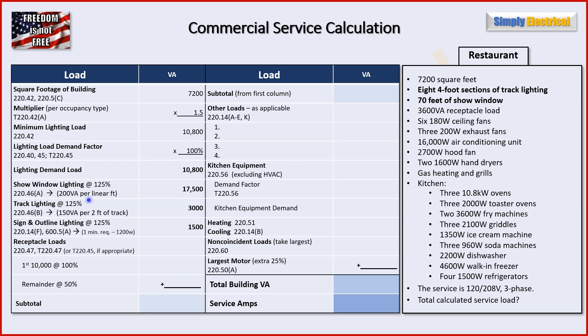Next, we jump into specialty lighting. For show window lighting, we have 70 feet times 200 VA per linear foot, giving us 14,000 VA. Since the show window lighting will be on for more than three hours, it's a continuous load, so we add an extra 25%, giving us 17,500 VA. For track lighting, per 220.46B we take 150 VA per two feet of track. We have eight four-foot sections — that's 32 feet, divided by two gives 16, times 150 VA equals 2,400 VA. With the 125% continuous load factor, that becomes 3,000 VA.